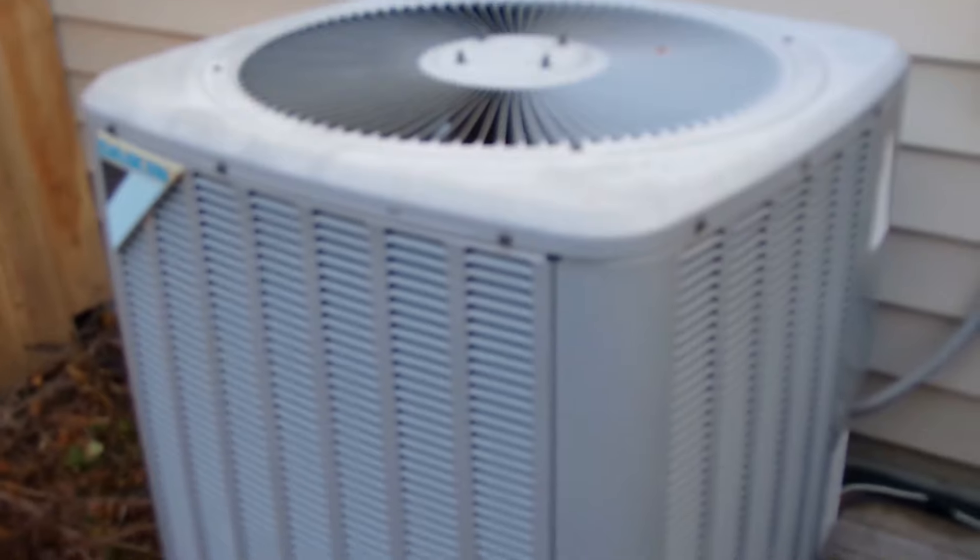I'll see if there's a way to set the cutoff temperature a little lower - I'd recommend maybe 30 degrees or so. Here down inside that one there's the reversing valve. Let's see where the reversing valve is - there it is. It's pretty tiny since it's a two-ton unit, but there are all the parts down there.